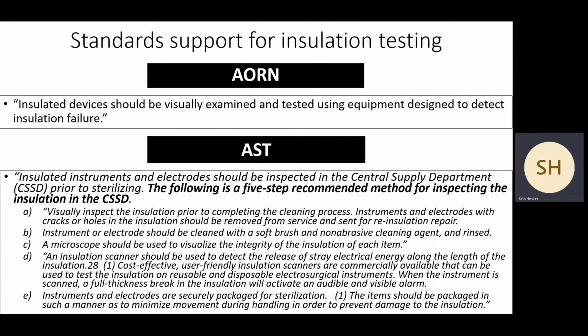AORN and AST, of course, weigh in. AST is big on this, and that's why I show a little more. They've been out ahead of this curve for a while, and a big piece of this has to do with preventing surgical fire. So you can imagine the Surg Tech organization is big into that. So AORN says insulated devices should be visually examined and tested using equipment designed to detect insulation failures. So they're going beyond the naked eye. AORN is saying there may be defects here that you might not be able to see with your eye, and there is equipment designed to detect leaks. So that's a good quality step to use.